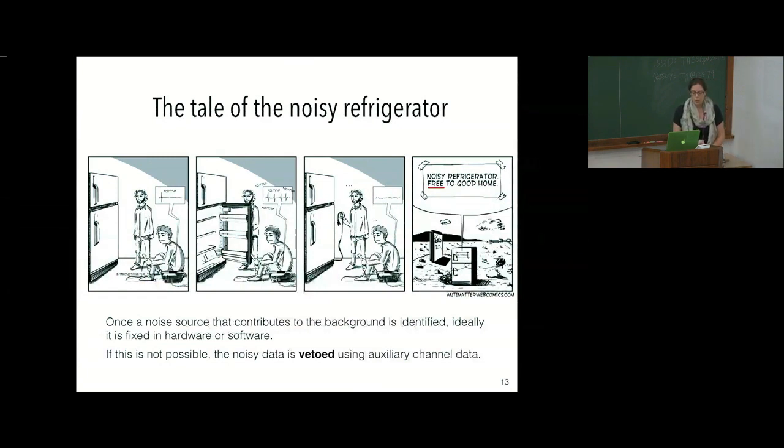So to give you a sense of how this goes at times, so this is a story that I like to tell that took place last summer. So this is summer 2015, so a little less than two years ago. So at LIGO Hanford, we noticed that there was a periodic, a semi-periodic glitch that happened exactly at 60 hertz. And it occurred about once an hour. And we always saw it with the magnetometers, coincident with the magnetometers, at the end of the Y arm. And we noticed that as time went on, that as the weather got cooler, the time between each one of these glitches kept getting longer. So we were thinking, okay, maybe it's temperature related. So eventually, two of these fellows, so this is Vinnie Roma and Orha, went down to the end station with a handheld magnetometer. And at the time that we predicted one of these glitches would happen, and isolated the source to a refrigerator that was holding cool water for people to come out of the vacuum chamber, dressed in their bunny suits, that never got unplugged.